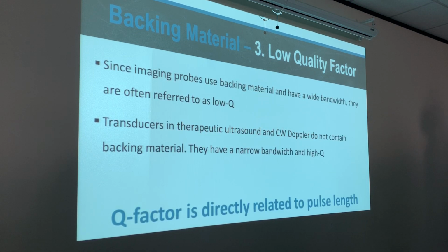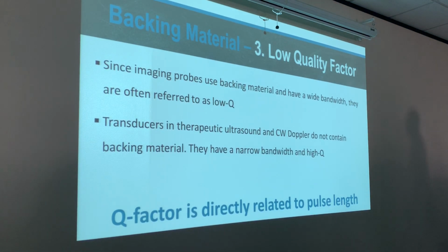So since imaging probes use backing material, they have a wide bandwidth. They are often referred to as low quality. Transducers in therapeutic and continuous wave Doppler do not contain backing material. They have a narrow bandwidth. They're operating closer to the main frequency.